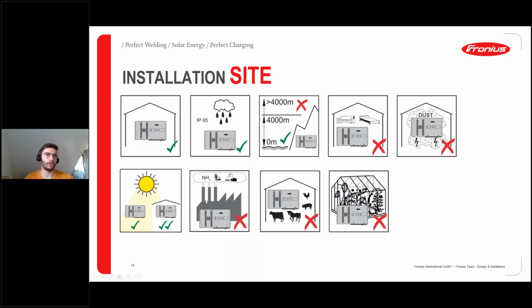We can also see a direct sunlight installation is possible with the Fronius Tauro. This is actually a first for our products, so installing it in direct sunlight next to the modules, for example, is no problem without restrictions. However, it's of course better to install it in a shaded area for an even cooler inverter and component. Both are possible, but it's better to install it underneath the modules or put a small cover or shade on top of the inverter.